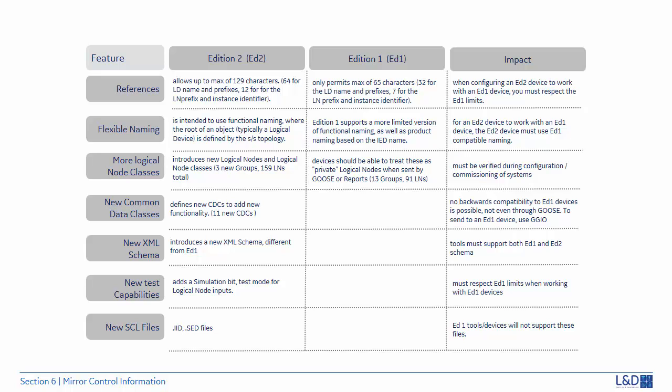On a final note, let's review the IEC 61850 features and how they compare between Edition 1 and Edition 2. In Edition 2, the size of the field names were doubled in size. So when you're working with Edition 1 and Edition 2, you must respect the Edition 1 limitation.